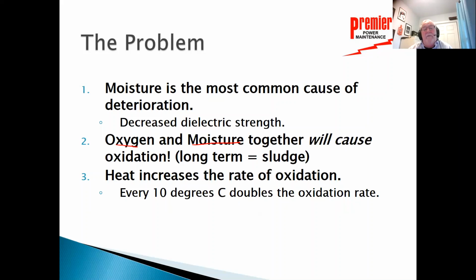And when oxidation begins, if it's not corrected quickly, long term, it will build into sludge. That sludge forms on the paper that's around our coil assembly inside the transformer. Part of the purpose of the transformer oil in the first place is to keep the temperature down. So now I've got sludge there, and I can't get rid of all the heat on that paper and coil assembly. And when the heat increases, the rate of oxidation increases. Every 10 degrees C doubles the oxidation rate. So if I have moisture and oxygen and I add heat to that, I'm on a death spiral, because now I'm just creating more sludge, which increases the heat, which is causing oxidation to increase rapidly.